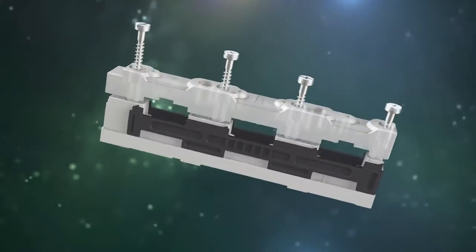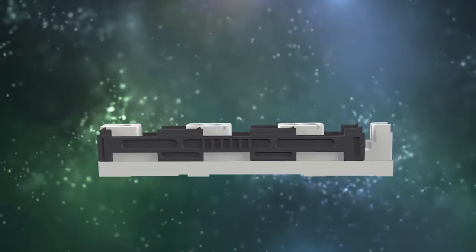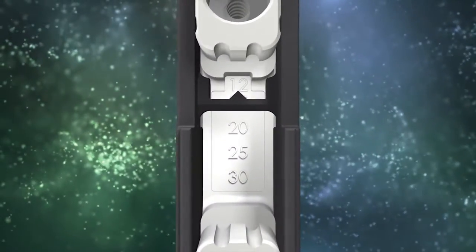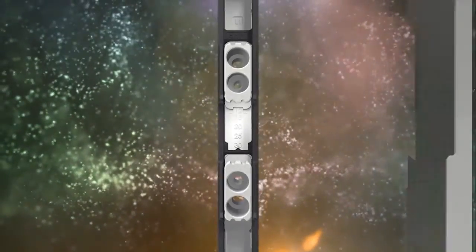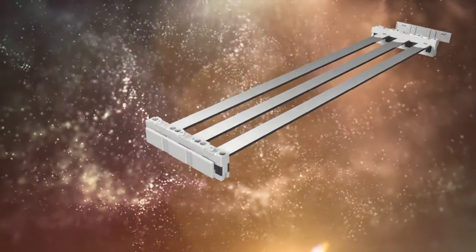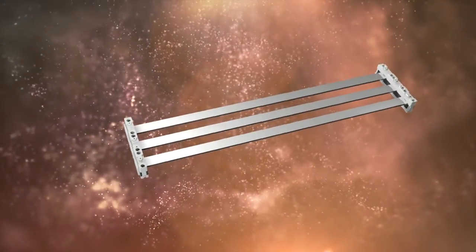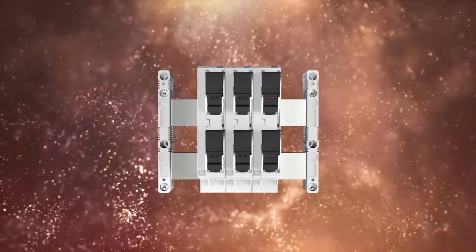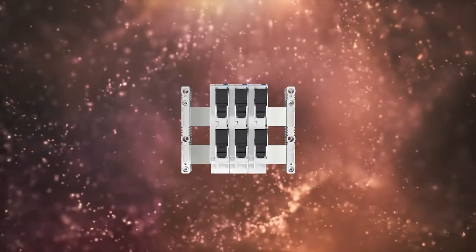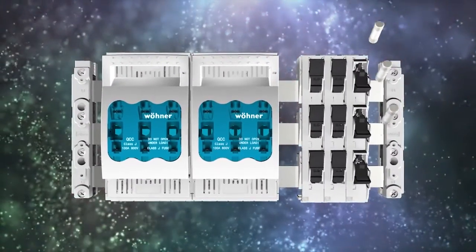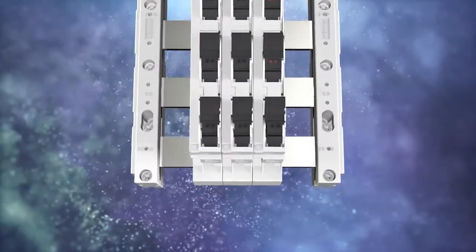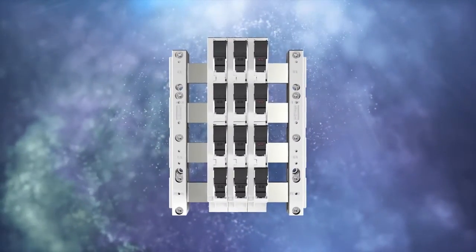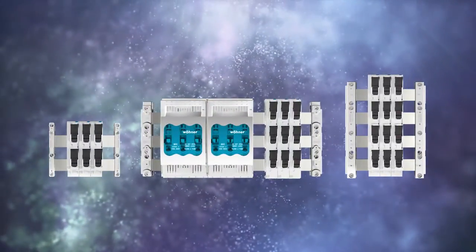For flat bus bars with a thickness of 5 and 10 millimeters, Wöhner has developed a universal bus bar support that can be adjusted to various bus bar widths. The slide can be adjusted to widths of 12 to 30 millimeters. The universal bus bar support comes in two-pole, three-pole, and four-pole versions. The two-pole system is used for photovoltaic as well as DC applications. For three-pole systems, Wöhner also offers fuse bases meeting American and French standards. The four-pole components can be used to construct compact switchgears that conform to individual international requirements.